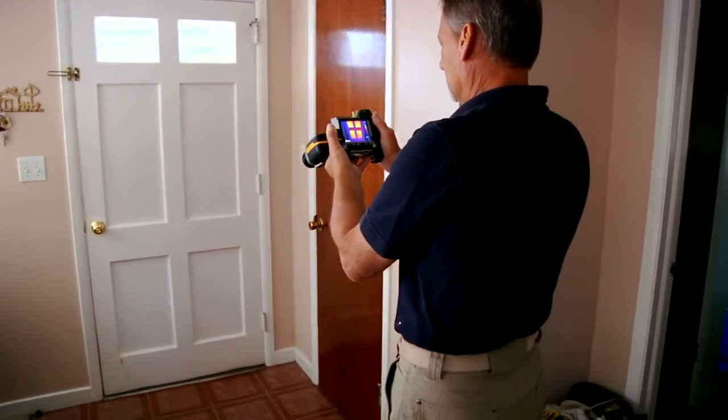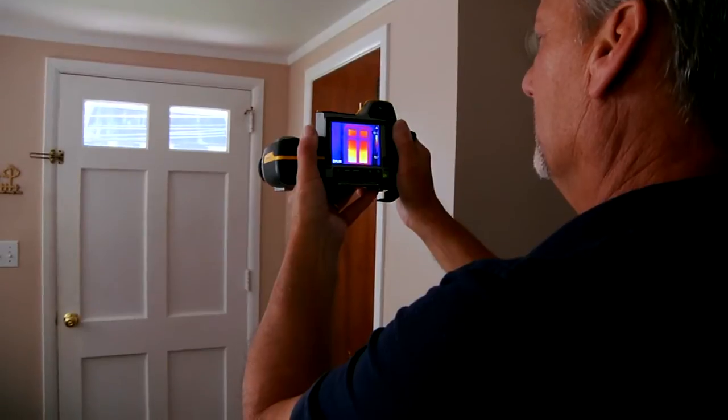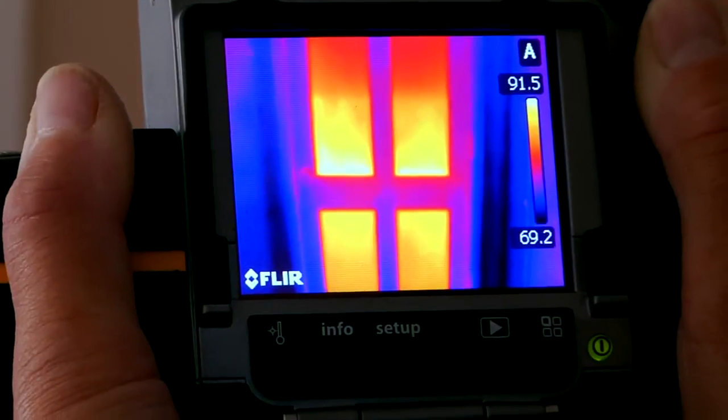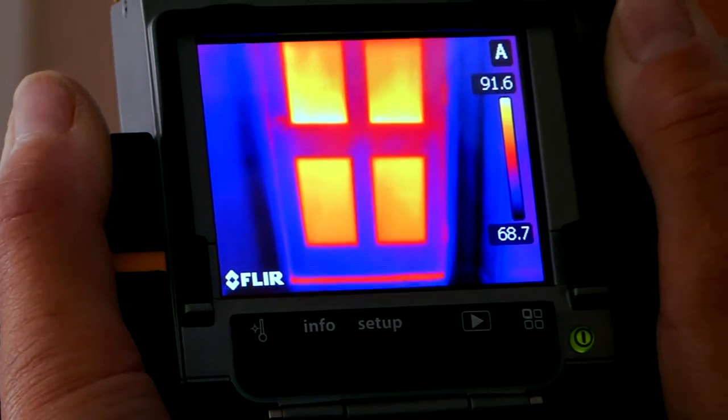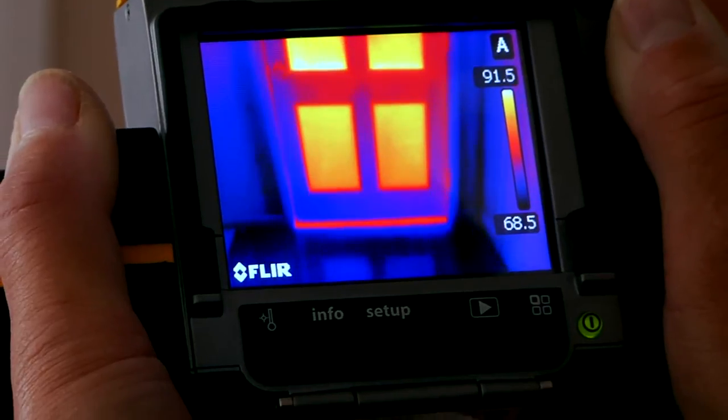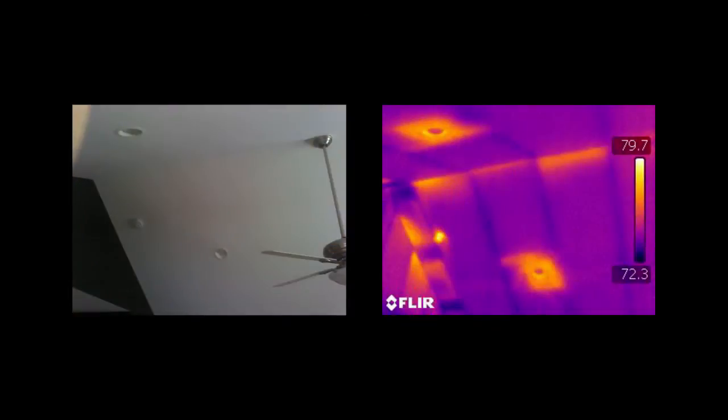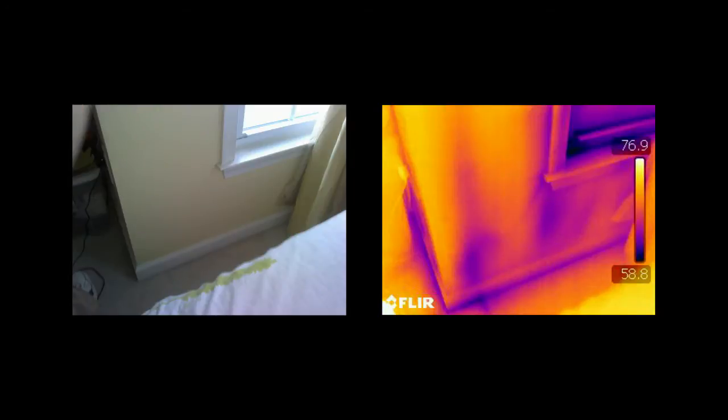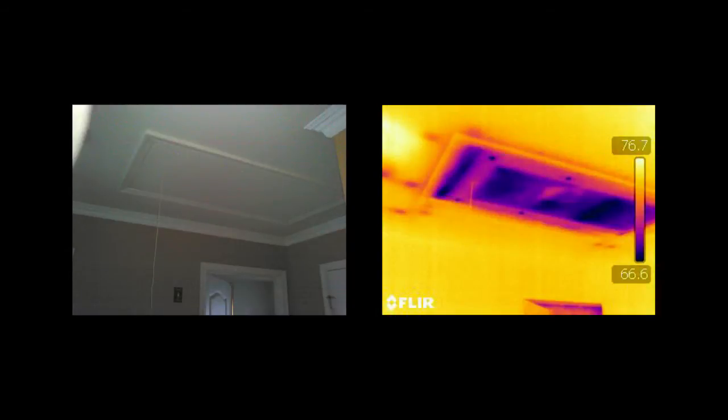Considering your heating and cooling load can be a substantial part of your actual energy budget, an infrared energy loss survey can be used to verify a number of energy loss culprits including missing, incorrectly installed, or inadequate insulation, leaks in ductwork, and much more.